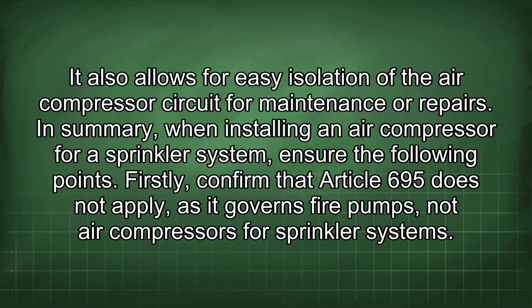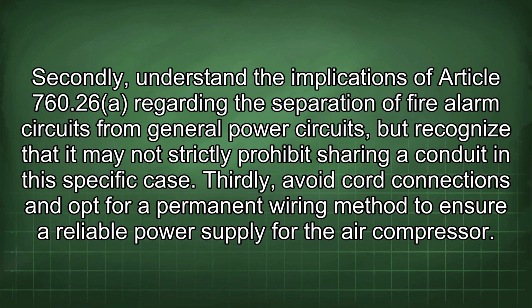In summary, when installing an air compressor for a sprinkler system, ensure the following points. Firstly, confirm that Article 695 does not apply, as it governs fire pumps, not air compressors for sprinkler systems. Secondly, understand the implications of Article 760.26 regarding the separation of fire alarm circuits from general power circuits, but recognize that it may not strictly prohibit sharing a conduit in this specific case.